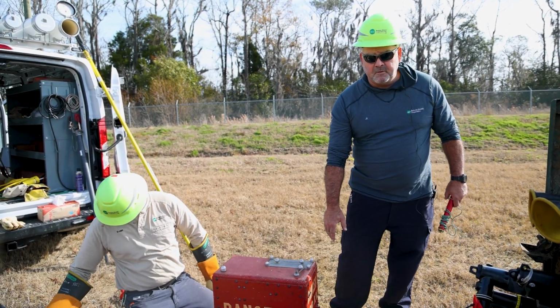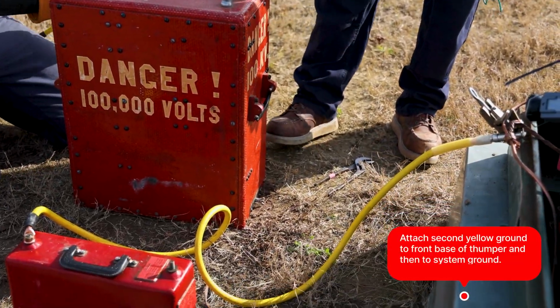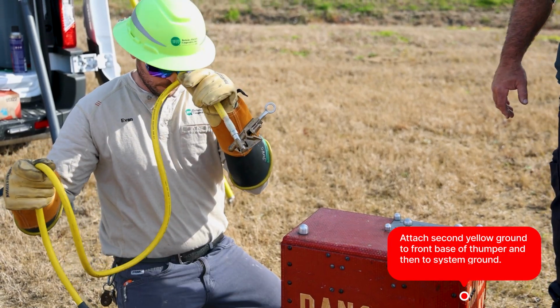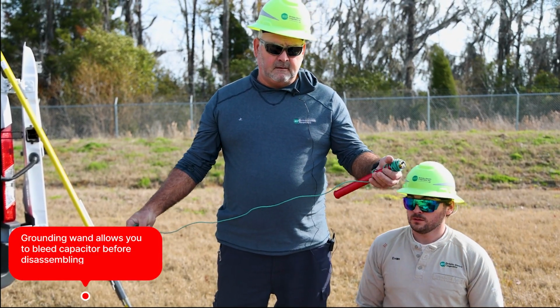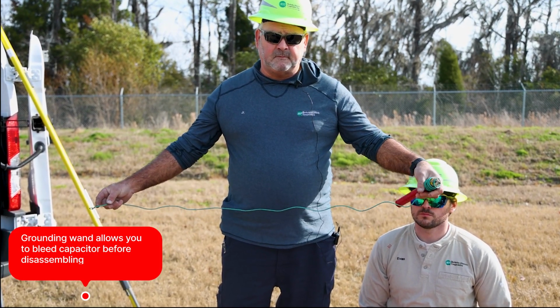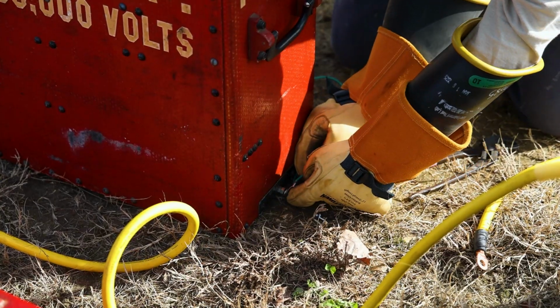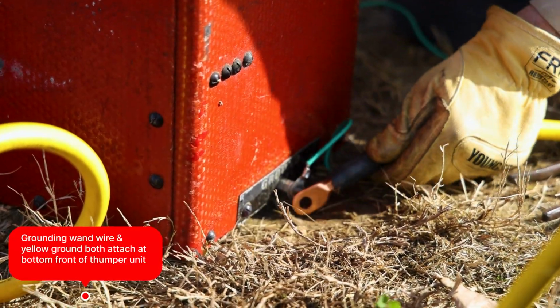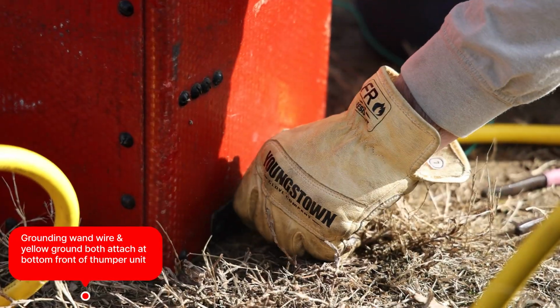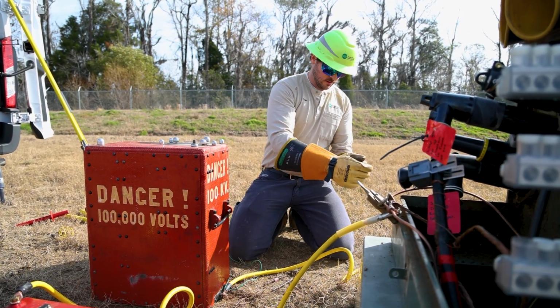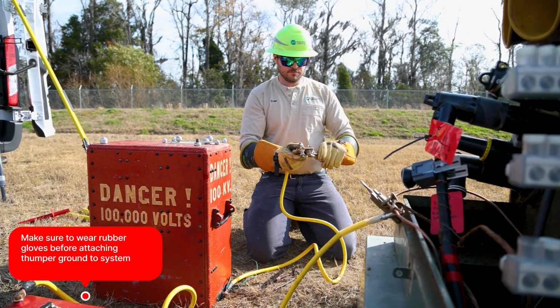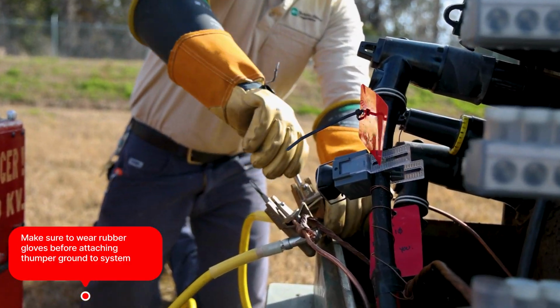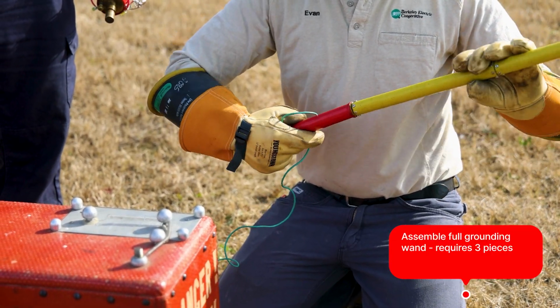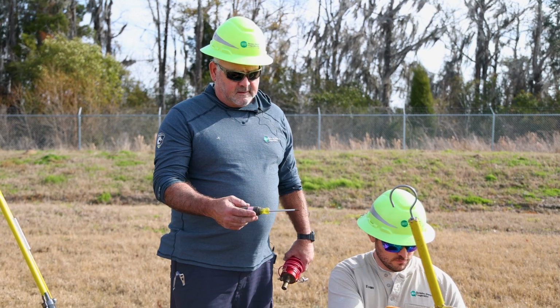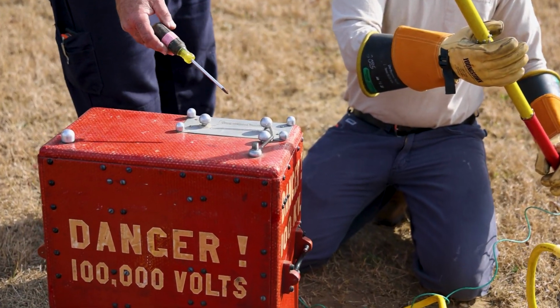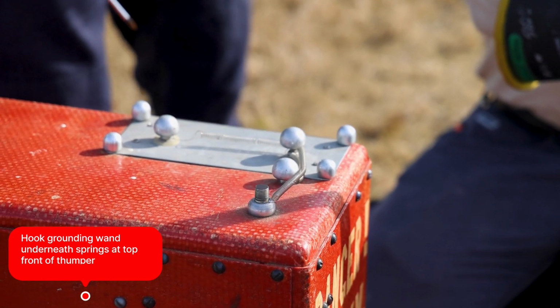Next step is you need to ground your thumper down here with one of the yellow grounds and then tie it to your system ground for your grounding wand, so that you can bleed the capacitor down before you try to disassemble it. Next step, you would be assembling your ground. You need to take your grounding wand and lay it up here. Best results is let the hook catch one of the springs right there so it holds it on top.